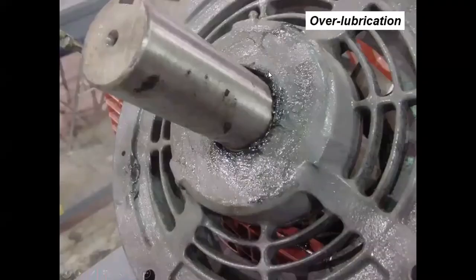Now, what could cause the windings to maybe be shorted together? It could be maybe that somebody actually put too much grease in that motor, and that grease has to go somewhere, and it can get into our windings and cause a short circuit. So whenever you lubricate a motor, you always want to go by the manufacturer's instructions. We have a lot of motors today that have sealed bearings, so we don't have to worry a whole lot about lubricating those. But still, a lot of motors do have regular bearings that we have to lubricate. You have to make sure that you have the right grease. You can't just put in any old grease you want, and then you have to make sure that you know how much grease to put in. A half a pump, 1 pump. You start going over 1 pump, you want to be really reading that manual that came with the manufacturer.